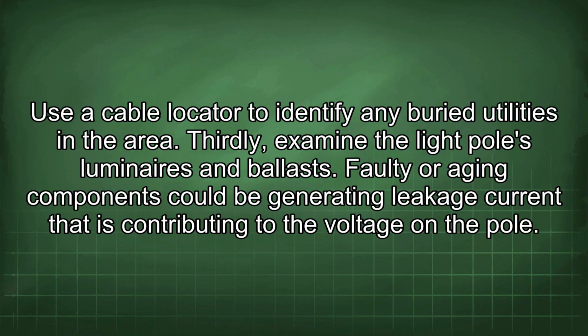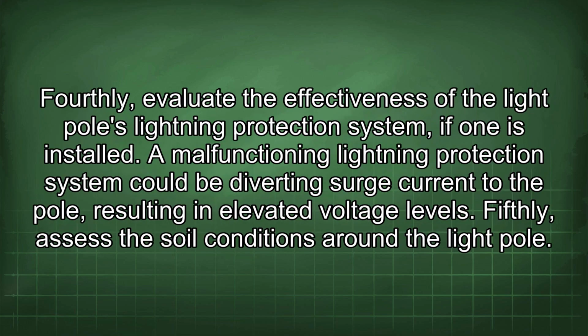Thirdly, examine the light pole's luminaires and ballasts. Faulty or aging components could be generating leakage current that is contributing to the voltage on the pole. Fourthly, evaluate the effectiveness of the light pole's lightning protection system, if one is installed. A malfunctioning lightning protection system could be diverting surge current to the pole, resulting in elevated voltage levels.